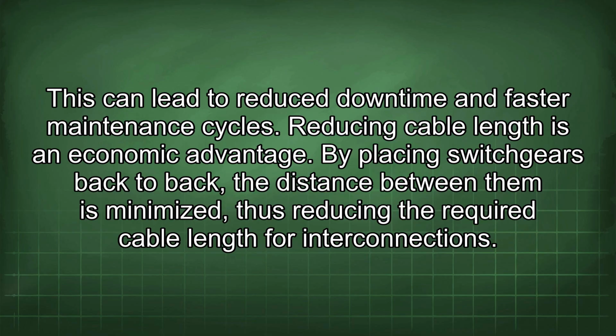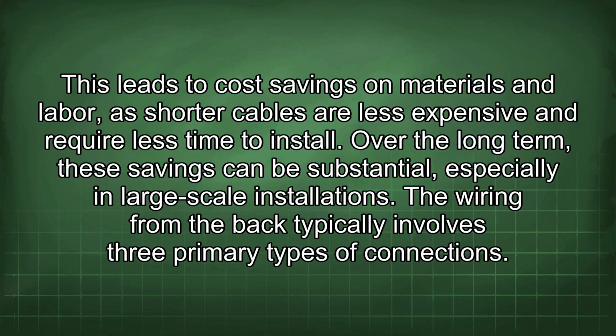Reducing cable length is an economic advantage. By placing switchgears back-to-back, the distance between them is minimized, thus reducing the required cable length for interconnections. This leads to cost savings on materials and labor, as shorter cables are less expensive and require less time to install. Over the long term, these savings can be substantial, especially in large-scale installations.